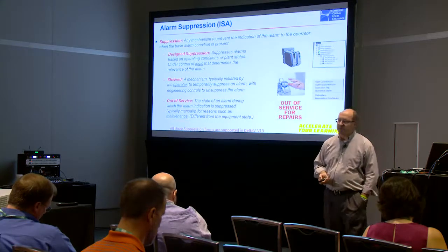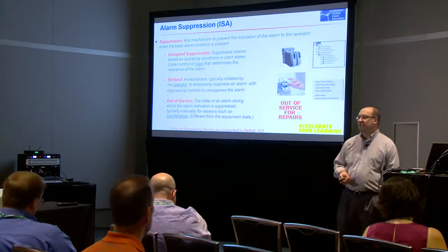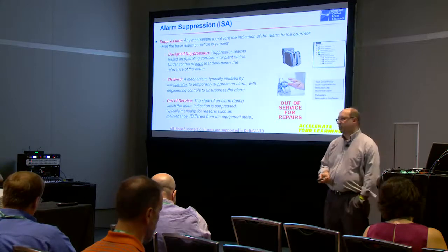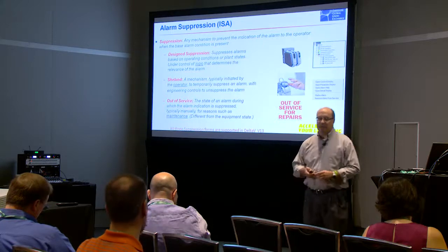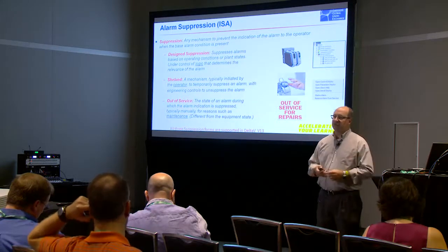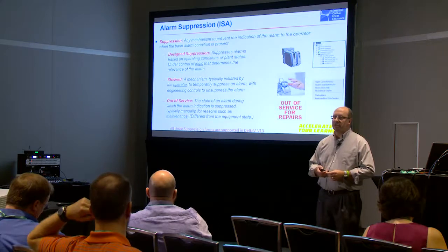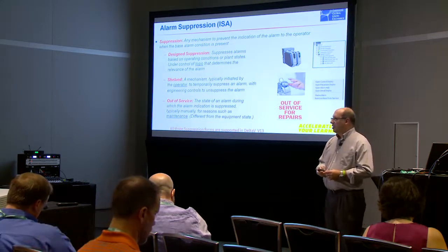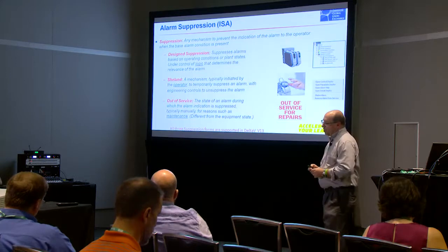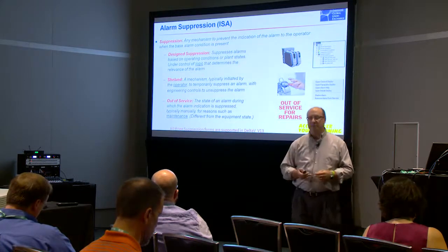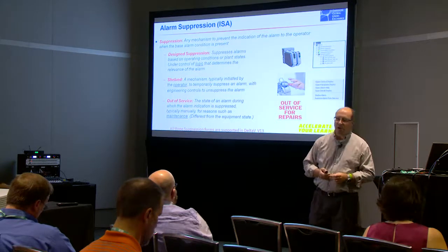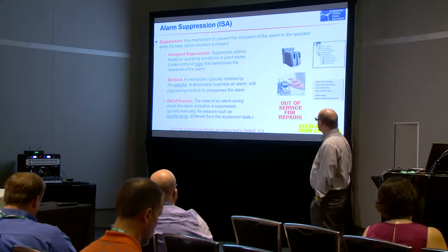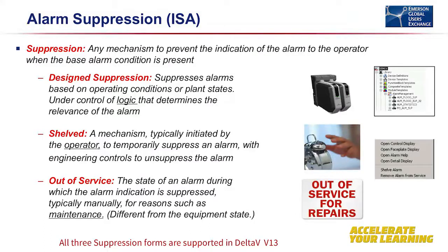The second type is called alarm shelving. This is like the snooze button for the operator. A nuisance alarm comes in, the operator realizes it's a nuisance alarm, it can't be fixed immediately, but he'd like to get it out of his field of view so it doesn't distract him. That's what alarm shelving would be for. And then maintenance is when you would take an alarm out of service for maintenance. So it's going to be suppressed for the long term to replace the hardware failure or a scenario like that we talked about. Now in DeltaV version 13, all three of these suppression scenarios are supported.